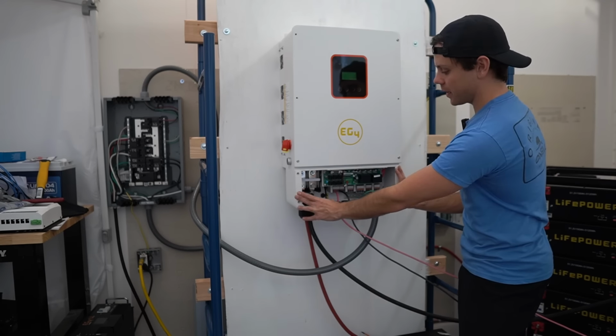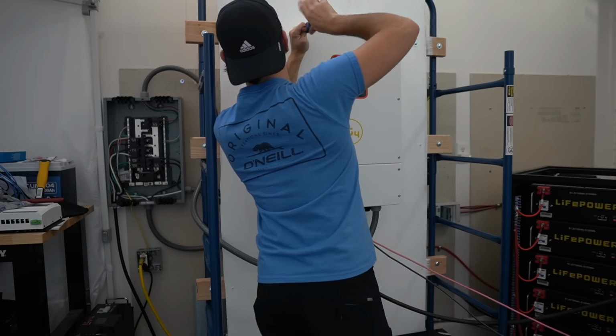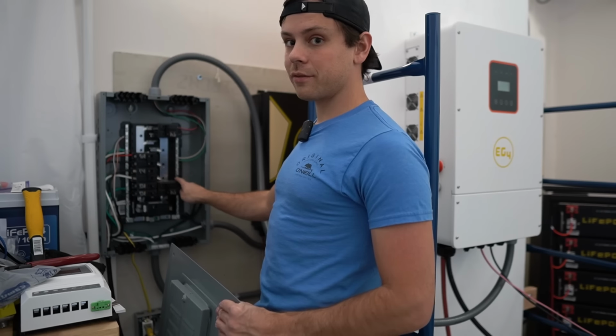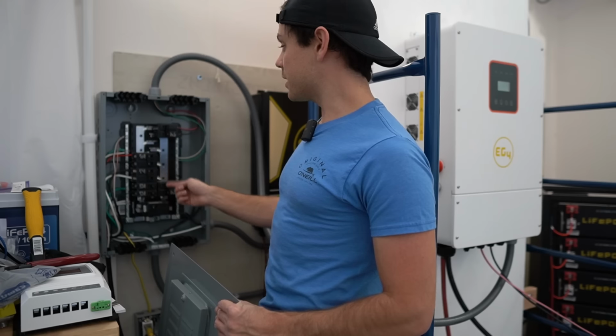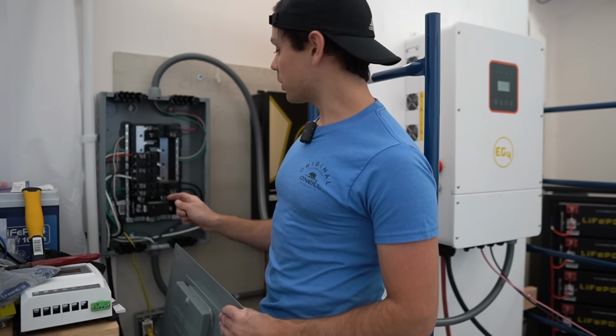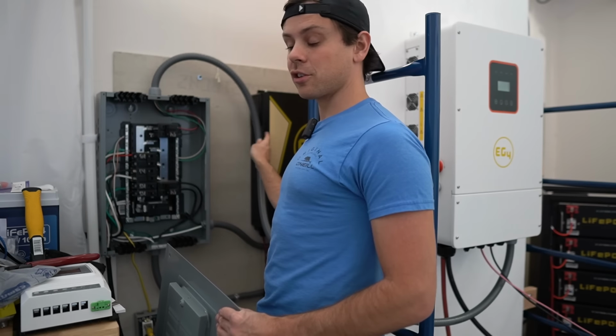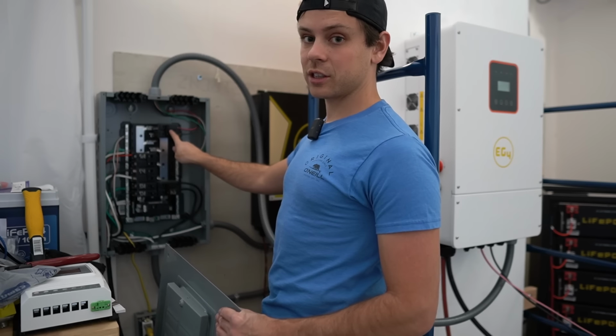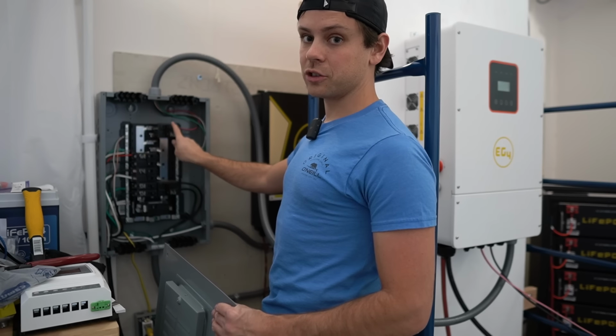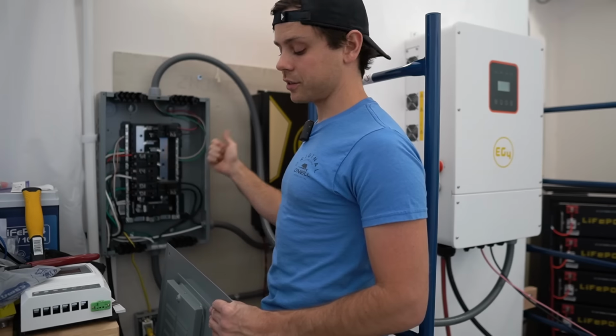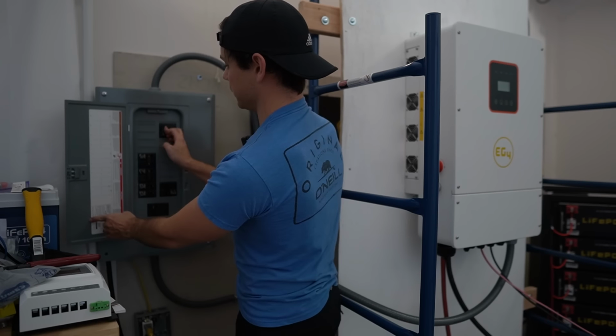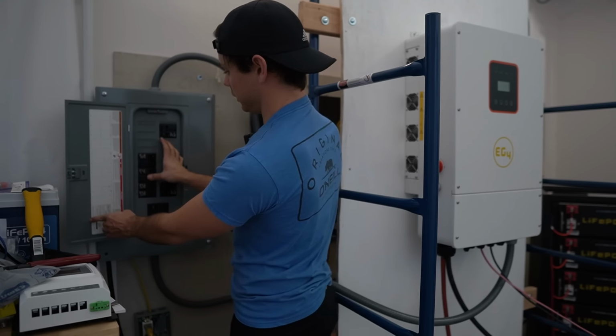So we're gonna put this cover back on and fire it up. Now realize we have 2 inverters that are not in sync that are feeding the same panel. So we're gonna keep this breaker for these inverters shut down, and then we're gonna turn this one on so we can power the loads just with this inverter, not the other system. So this one's off, this one's on, and we're gonna turn on the loads.